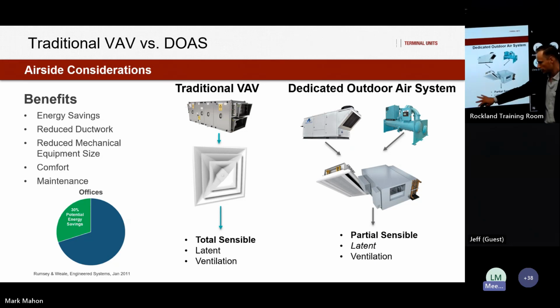The big rationale here is total sensible and latent and ventilation through a traditional VAV system. We're seeing, for the air side, partial sensible, so we are getting some sensible cooling because the air is colder than the space set point, but latent and ventilation being the critical requirements of the DOAS air system instead.